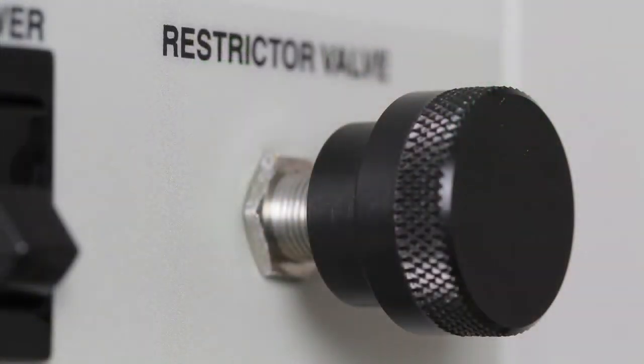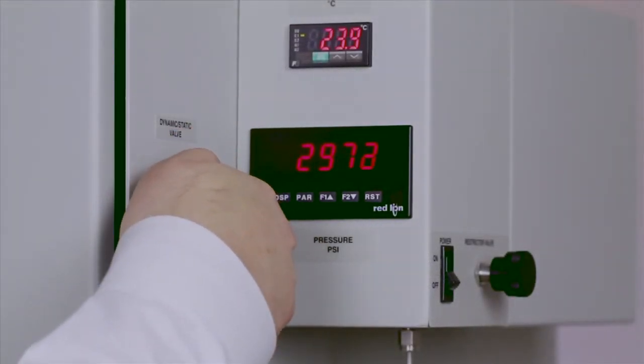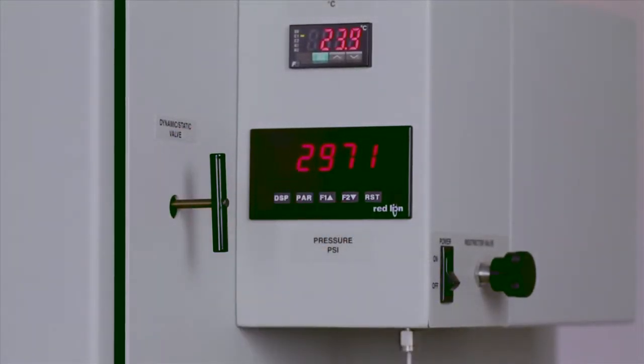Please note that the restrictor valve is not an on-off valve. Always use the static dynamic valve as the on-off valve. The restrictor valve is a sensitive micrometering valve, and small changes in the open-close position cause variance in the metered flow through the valve. Adjust the restrictor valve slowly to best meter the outflow of liquids from the SFE unit into the collection assembly. Never try to close it down tightly. To achieve a complete extraction, carry out several dynamic flow and soak steps.